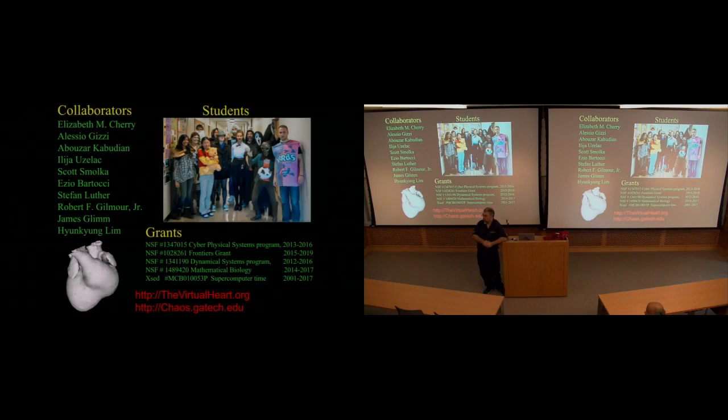But these algorithms are always extremely conservative, because you can never have a false negative, since the patient dies if you don't deliver the shock and there's VFib. But if you have something supraventricular, like AFib, it'll still sometimes deliver a shock when it's not needed. These are called unnecessary shocks, or there's another word for it. Anyway, they're false positives, basically, and they're very painful, and as you said, they cause damage to the heart.